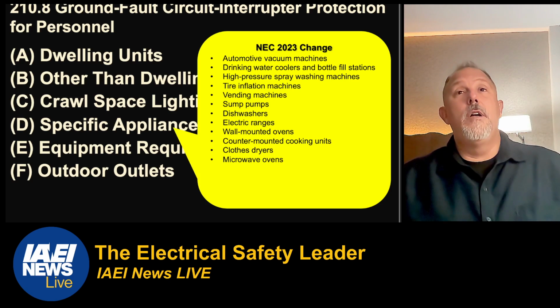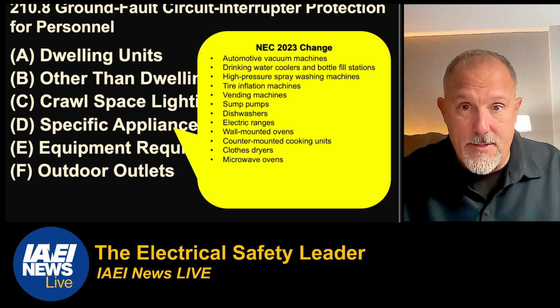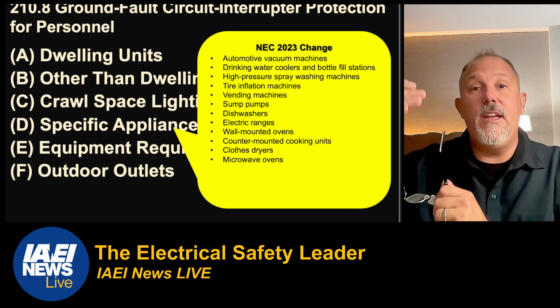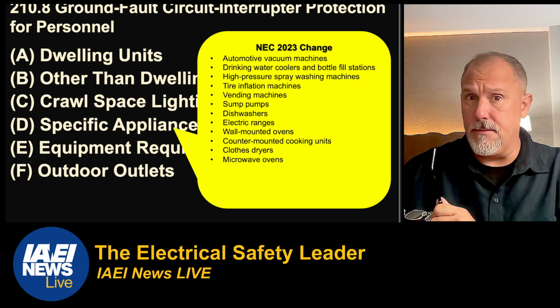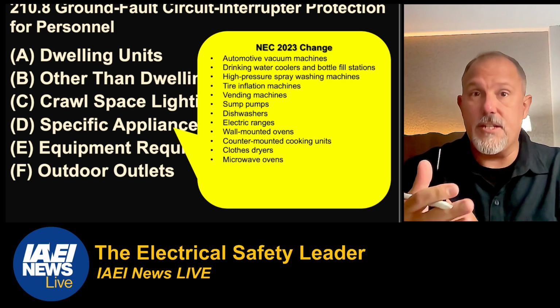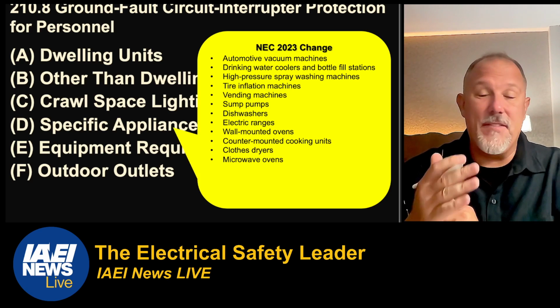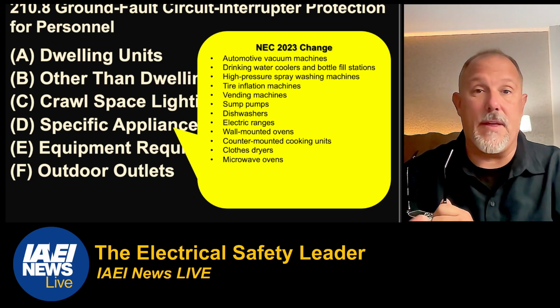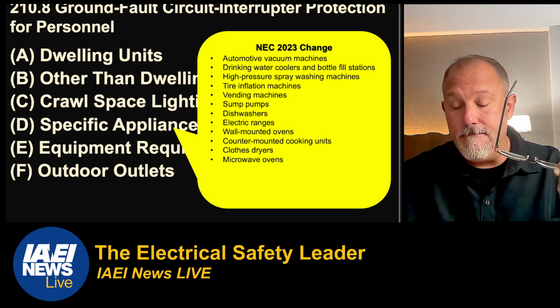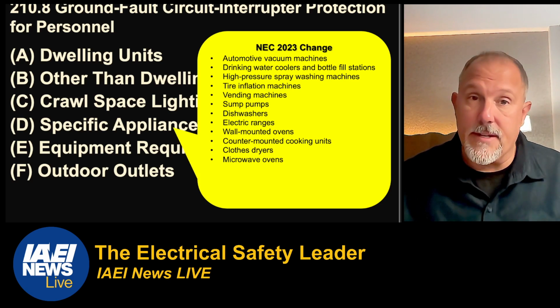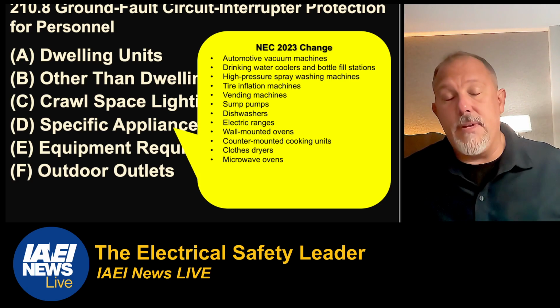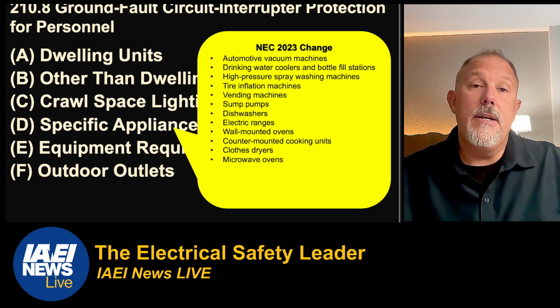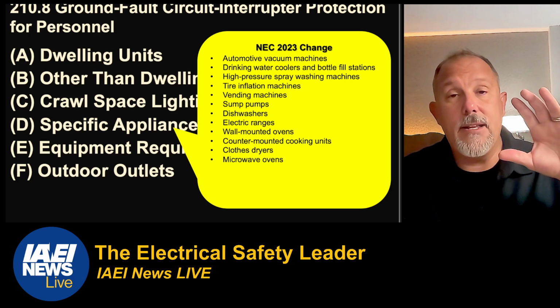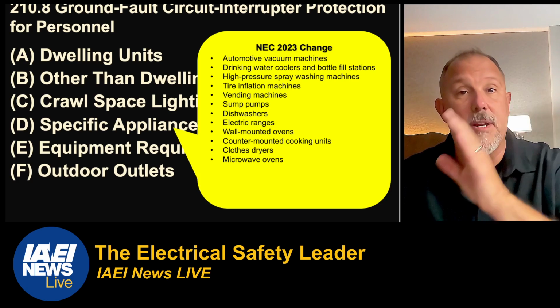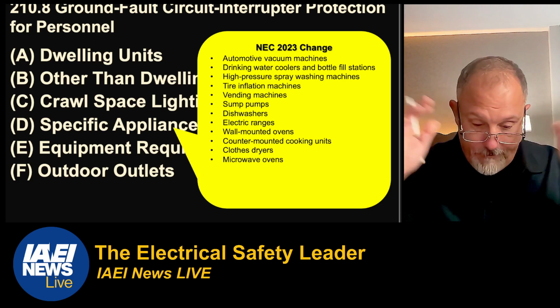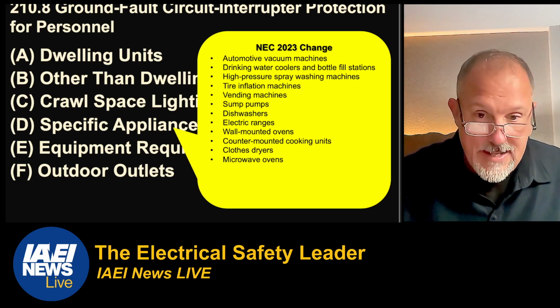And I know it drove concerns about leakage current. So here's what happens with leakage when you put these types of requirements on. If any of these appliances use that equipment grounding conductor, it's going to cause a GFCI to trip. Obviously, we're not supposed to use the equipment grounding conductor for anything other than fault currents. Article 250 tells us that. So are there some appliance manufacturers who are concerned about this? Yes, absolutely. But the appliance standards are changing, and many of the appliances are addressing this from a compatibility perspective. So that's all I'm going to say about that.